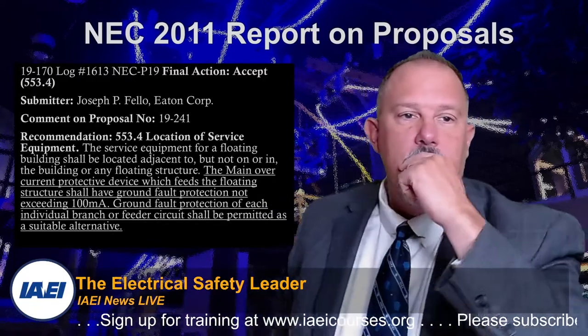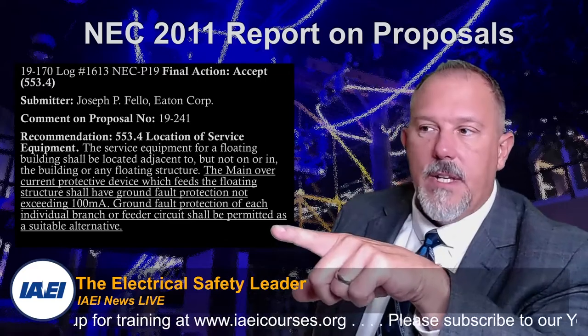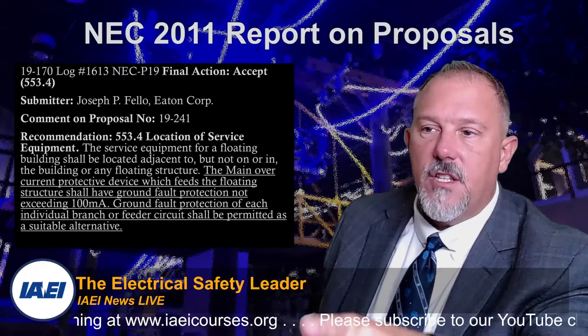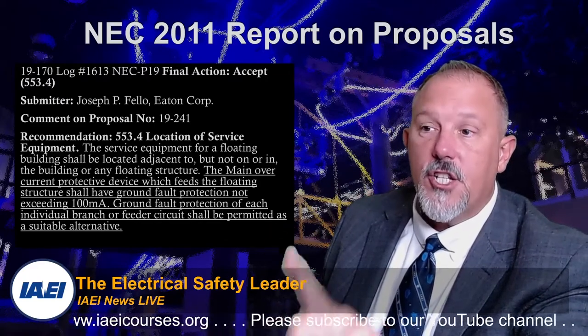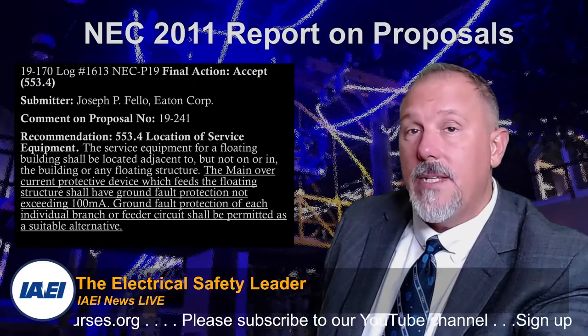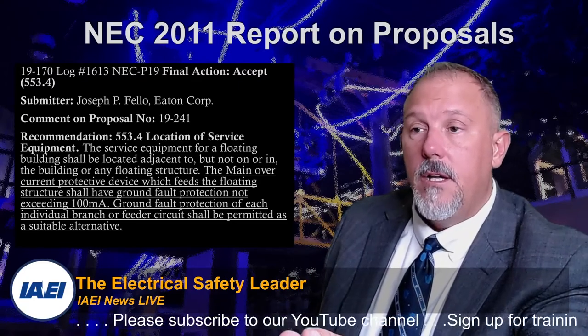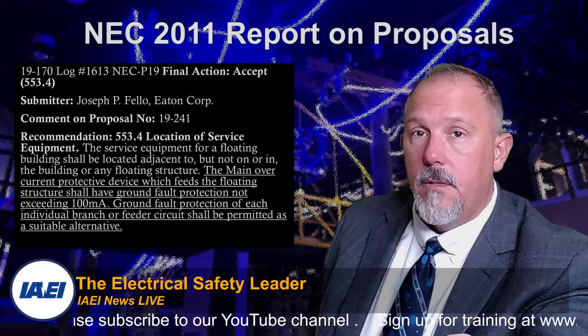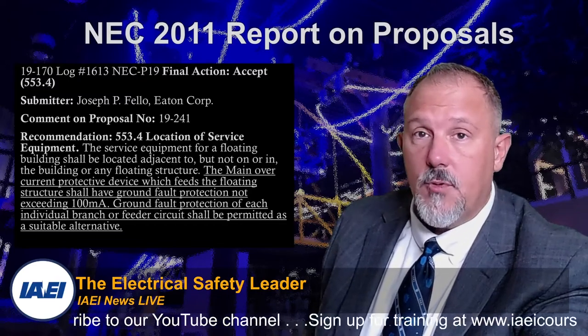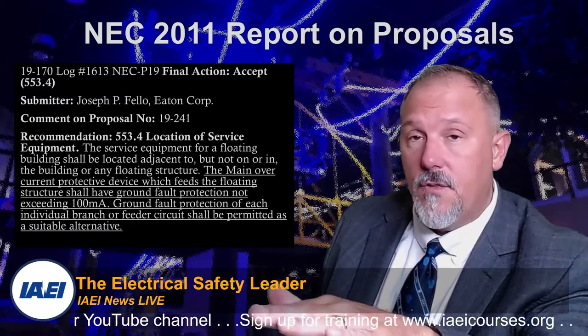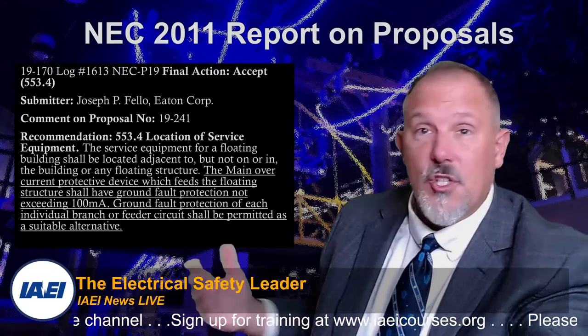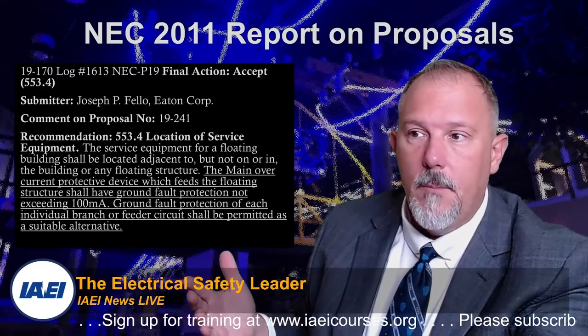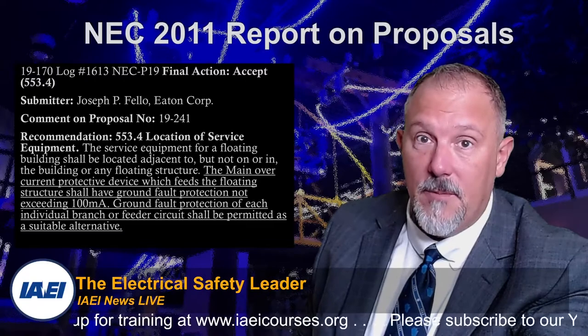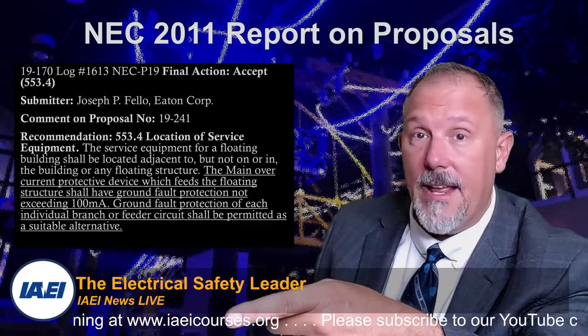So what we said was the main overcurrent protective device which feeds the floating structure shall have ground fault protection not exceeding 100 milliamps. What does that mean? That means 30 milliamps will work, GFCI 4 to 6 milliamps will work. There was no excuse for the code panel to say there was no product available, because there was product available on the market with that language.